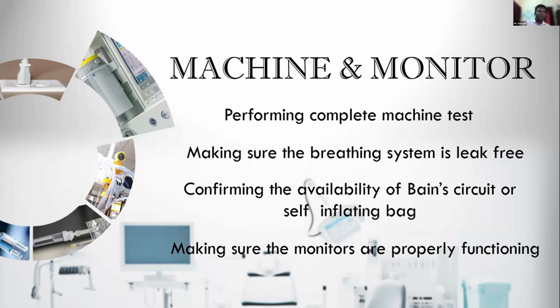Apart from checking whether the machine is fine, we have to have a backup plan. We make sure there is at least one, either a Jackson Rees for a pediatric patient or a Bain circuit for an adult, along with a self-inflating or ambu bag present inside the theater in case oxygen or anything fails. Having a backup plan, being prepared for any cause, is really important, and in our institute it is always present in every theater.